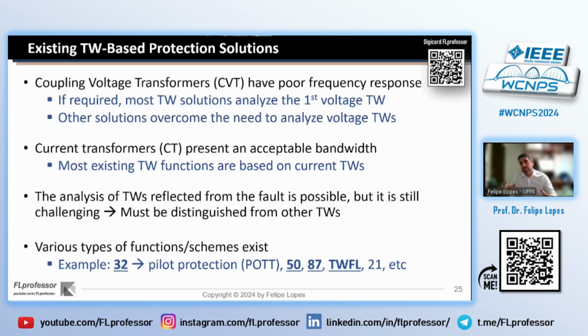So it has somewhat limited the use of reflections in protection solutions, although we hope to see something in the future. Given this context, various types of functions and schemes have been proposed. For example, we can find the directional elements, which have also been used to implement pilot protections like the POTT scheme. We have seen overcurrent elements, differential elements, fault location, distance protection, but distance protection requires the detection of reflected waves, so they are not yet in off-the-shelf devices. But these other schemes we can implement using existing technologies already.